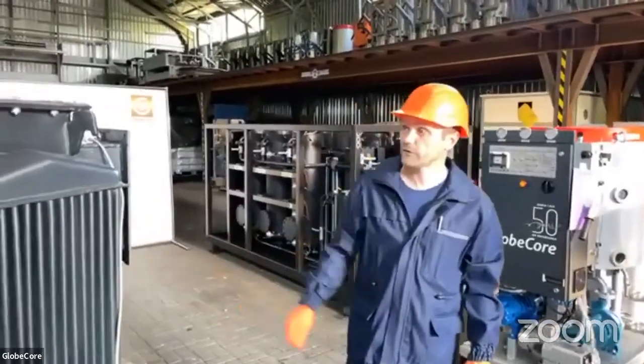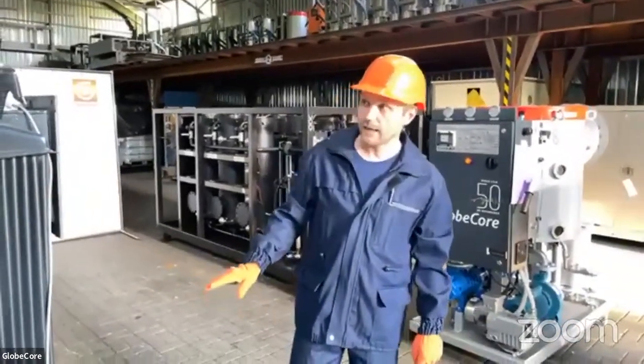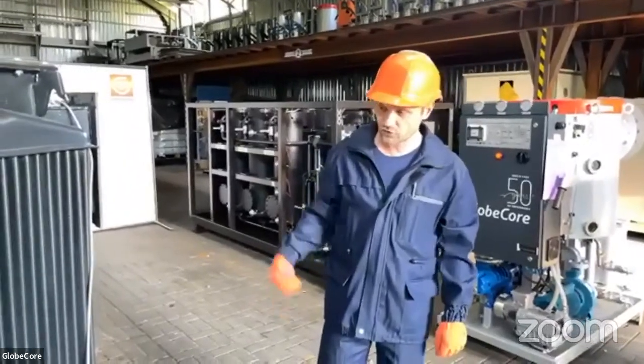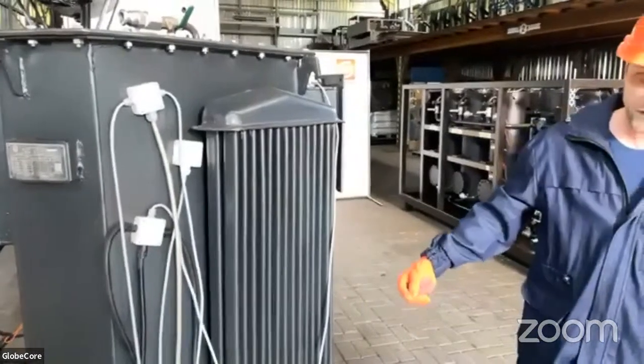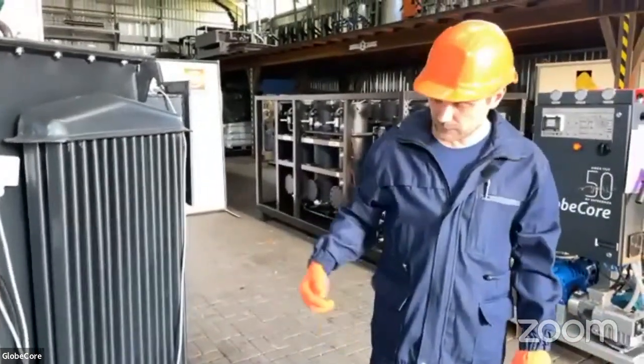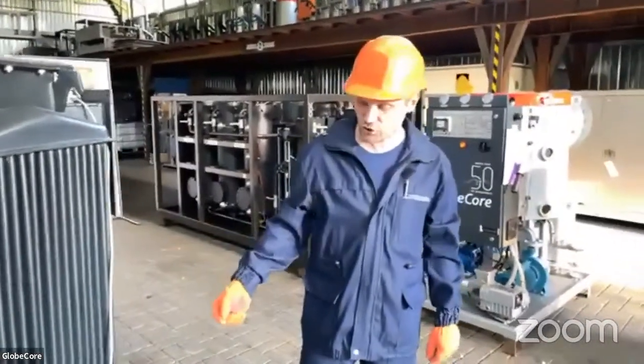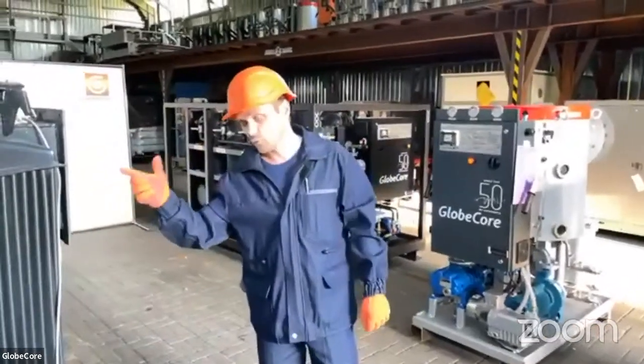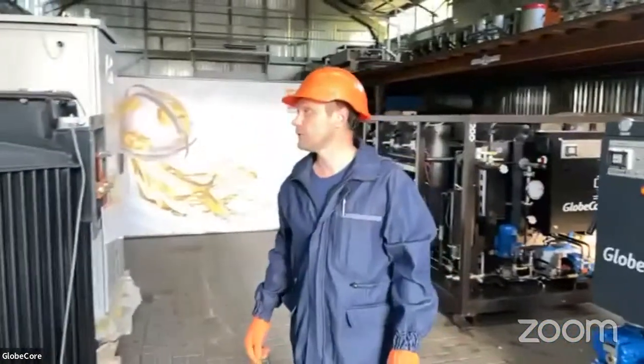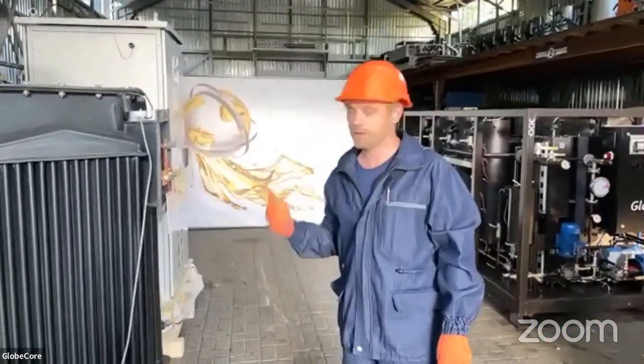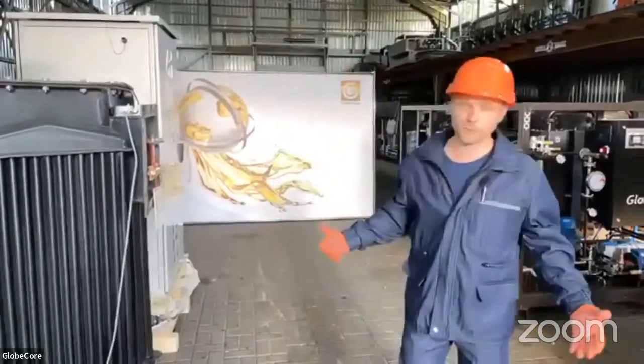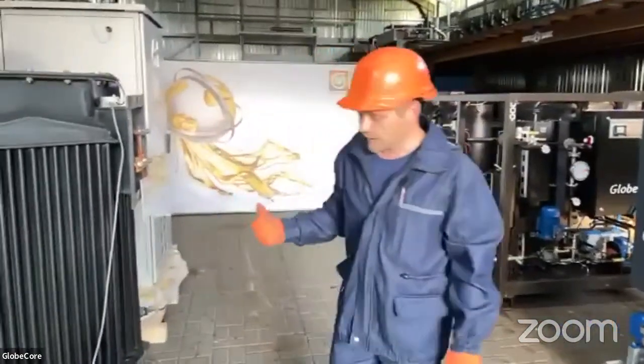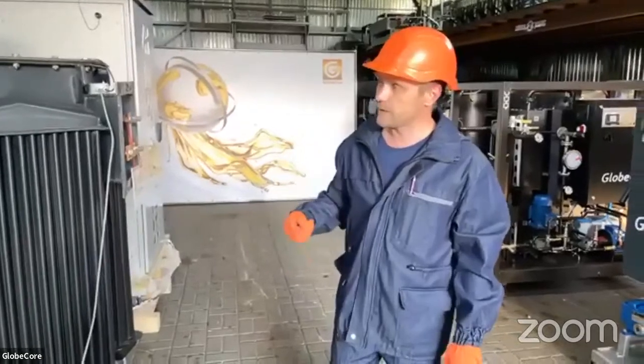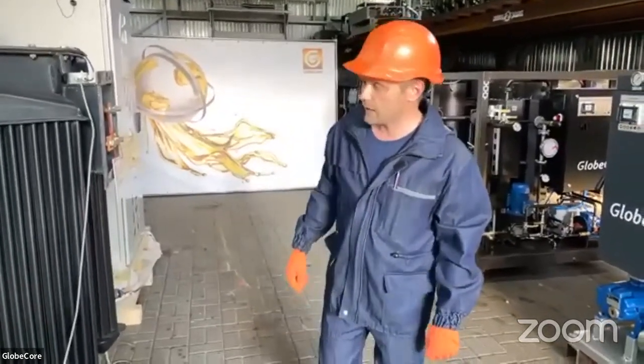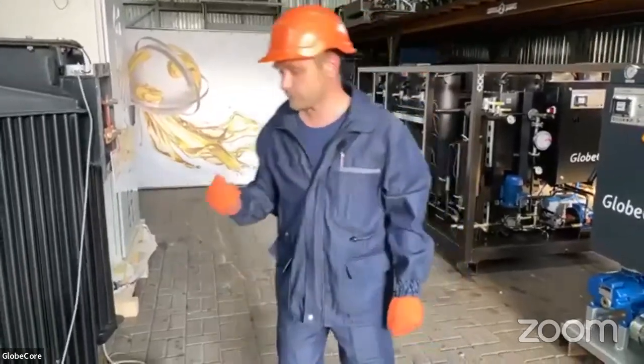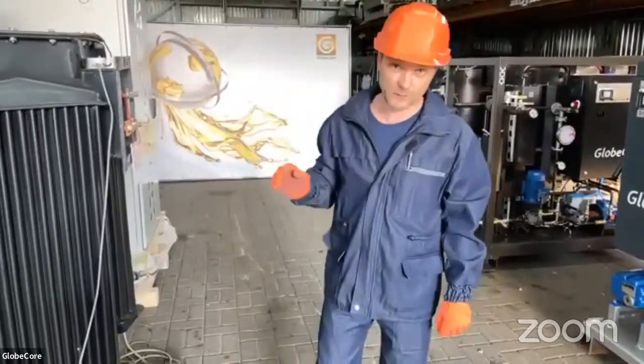run low frequency heating with no interruption, and it enabled us to check the moisture content at the end of the day when we stopped the drying process, and to see its change in the morning when water was extracted during the low frequency heating operation, the night time. So what we have seen, let's say at the end of the day, we had something like 10 to 20 ppm moisture, and the next morning we observed values like 100 to 120 ppm.